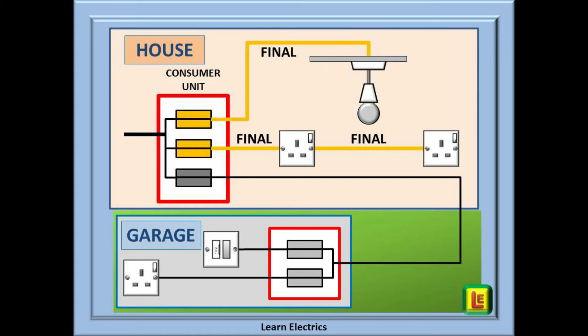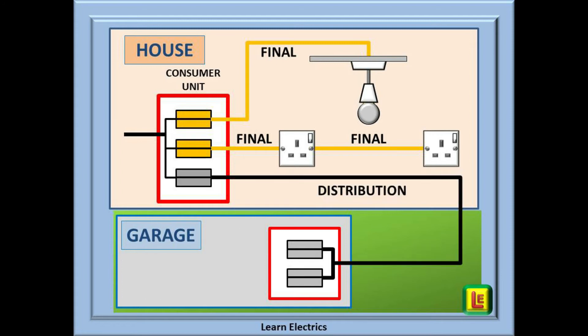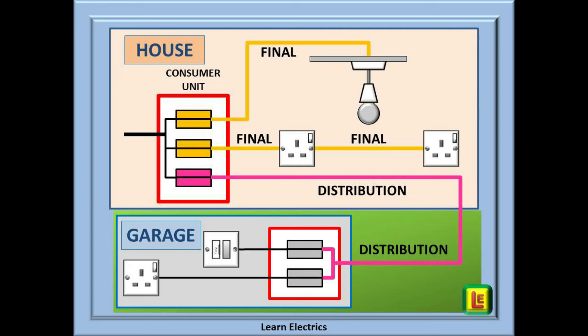Now we need to supply power to the garage. We will install a small consumer unit or garage unit in the garage, with the feed to the garage unit coming from the house consumer unit. From the garage unit we can have sockets, lights, or whatever. Because the cable is between two consumer units — two sets of fuses — it is now a distribution circuit. It is still distributing electricity and has not yet passed the last consumer unit. Let's identify this with a pink colour: pink for distribution circuits.